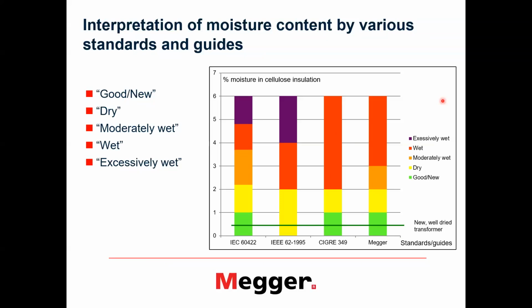There are different methods, right? There's another one based on heating the core with low frequency signals and then extracting the moisture. But heating the oil, right? There's specific equipment in the field that will remove the oil, heat the oil, and sprinkle hot oil on top of the core, and then by applying vacuum, the vacuum pumping will be extracting the moisture, and you will be controlling the moisture extraction.